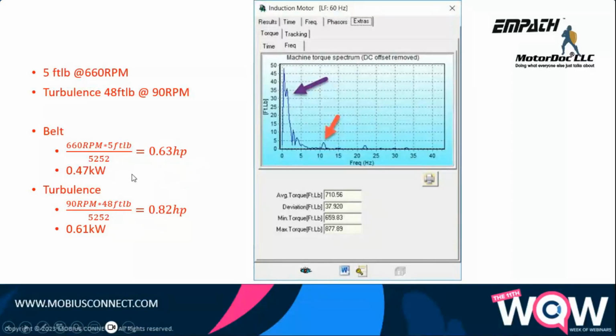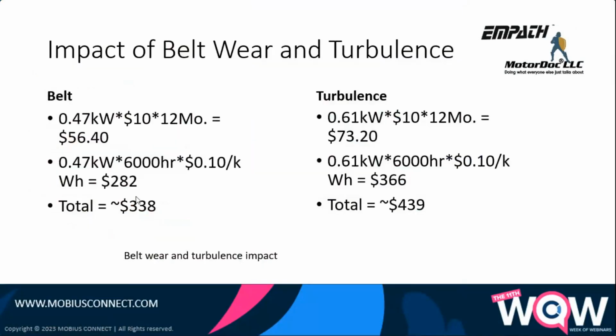So this is a relatively small value, thank goodness, so it appears. But if I take that, just a little bit of belt wear, that's really what it is, just a tiny bit of belt wear, 0.47 kilowatts times $10, $56 a year in demand, times 6,000 hours times 10 cents per kilowatt hour, 200. So about $338 for the belt loss. So I can make a decision whether I continue using that belt or do something with it then.